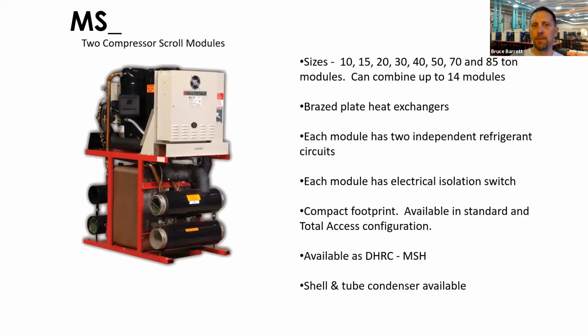All right, so we're going to go through some different models that describe our offerings. The most common is our scroll compressor, 10, 15, 20, 30, 40, 50, 70, and 85 tons. Those can be stacked all together up to 14 modules. They are braze plate heat exchangers, 2 independent refrigerant circuits. They do have electrical isolation. Not sure if you can see my cursor here, but you can power off individual modules and not disrupt the rest of the array.